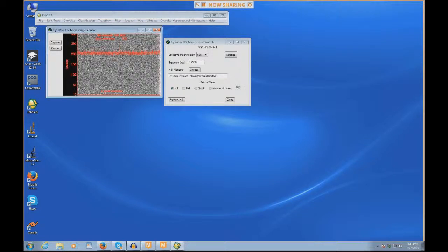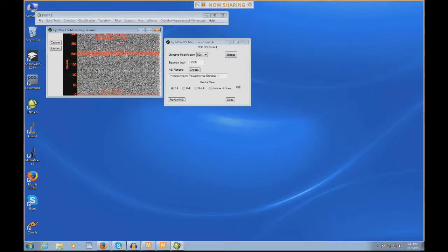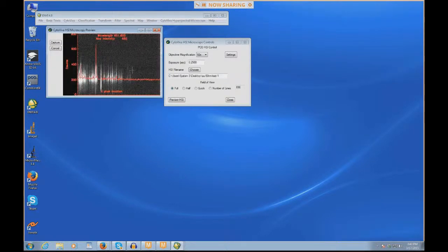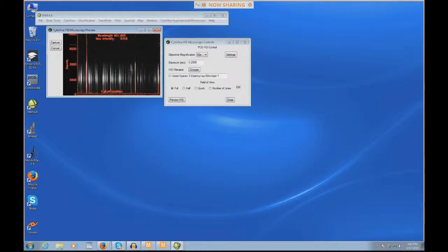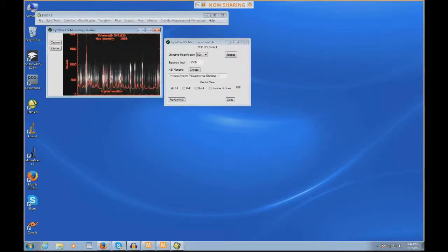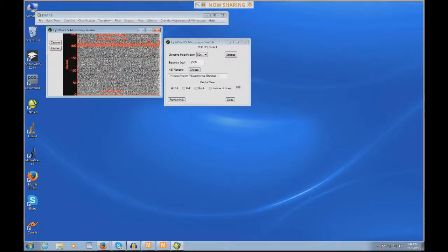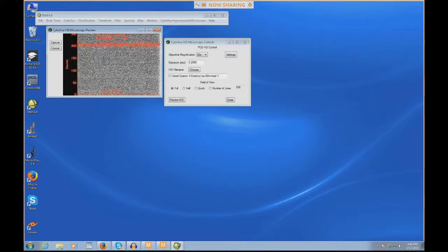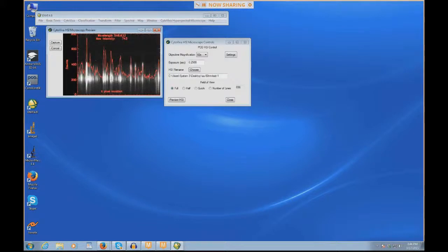Make sure that you're seeing your data in the preview window. Make sure to check the slide bar on the trinocular head, and then also check the slide bar on the dual-camera port. If you go to the left, the data goes away because now all the light is being routed directly up to the optical camera on your system. To the right directs the light to the back, and that would be the spectrograph. Check these things. If you don't see this in the preview window, if it looks like static on a TV, make sure to check the path of the light and make sure that all of the slide bars are in the appropriate positions.